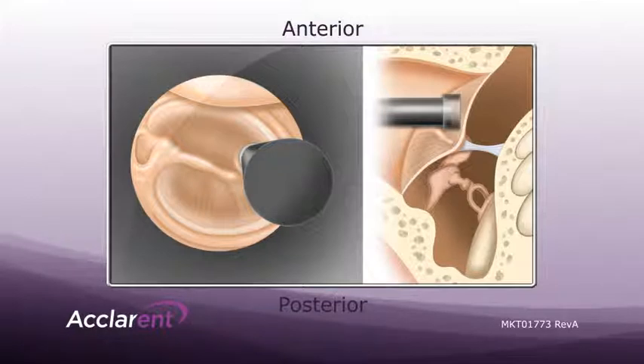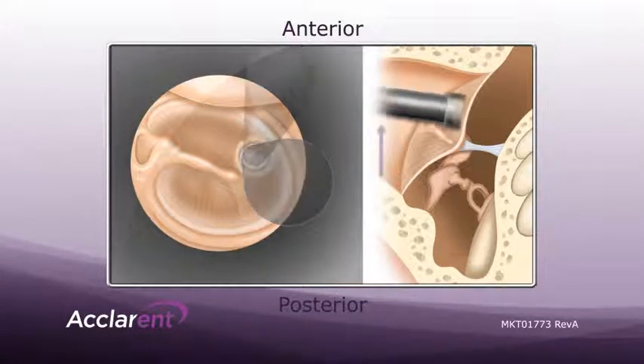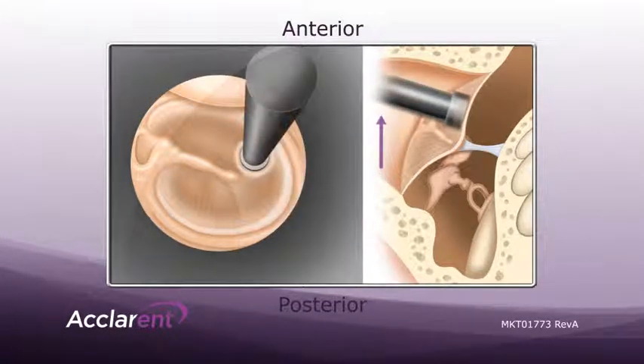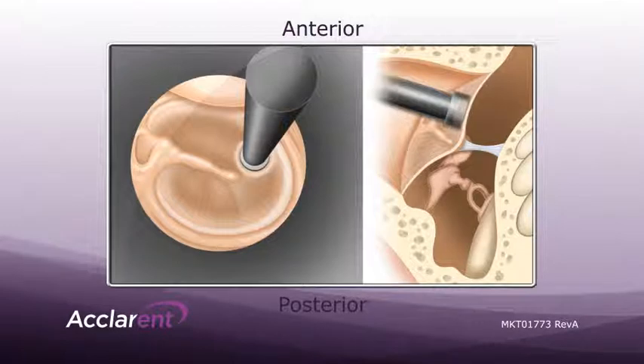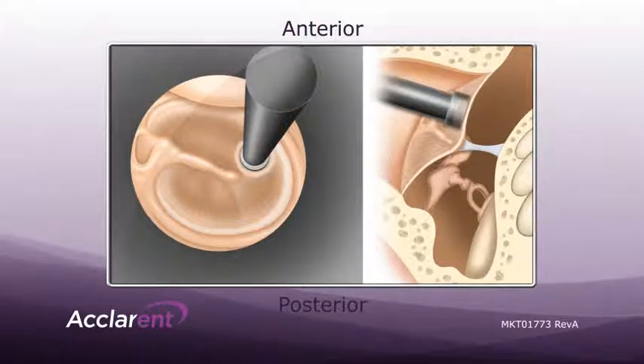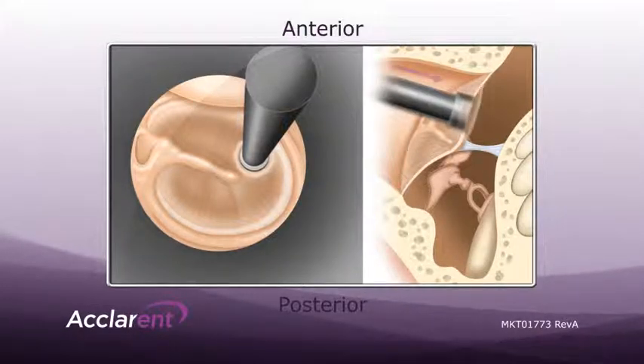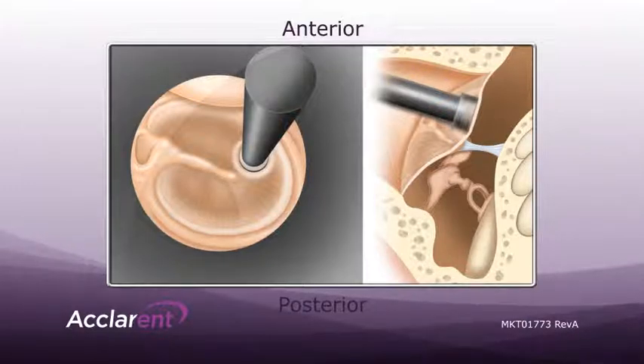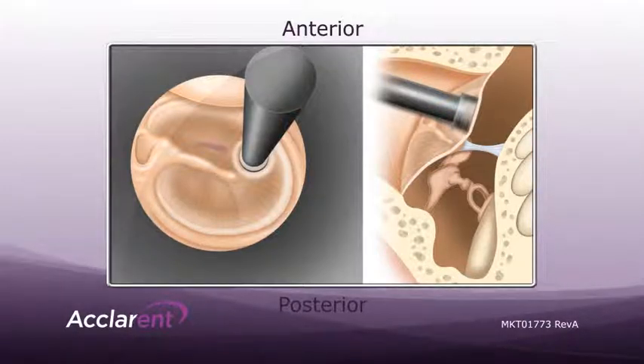If needed, change the angle of approach so that the device tip is flush against the TM. If apposition is still not achieved, apply gentle pressure against the tympanic membrane. A good visual indicator that full contact has been made is the shifting of the light reflex around the tip.